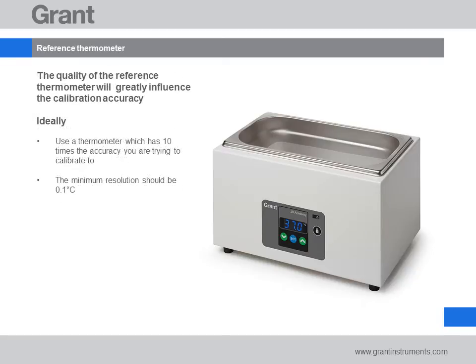The quality of the reference thermometer will also greatly affect the accuracy of the calibration. Ideally choose a thermometer which has 10 times the accuracy you are trying to calibrate to, and with a minimum resolution of 0.1 degrees Celsius.